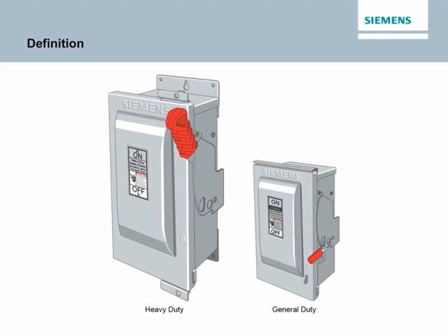A safety switch is a common type of enclosed switch. Safety switches are generally used for 2 purposes: 1, as a disconnecting means for a service entrance, or 2, as a disconnecting means and fault protection for motors. The enclosure provides a degree of protection to personnel against incidental contact with live electrical equipment. It also provides protection to the enclosed equipment against specific environmental conditions. Safety switches may consist of a switch only, or may consist of a switch and fuses. There are 2 families of Siemens safety switches, general and heavy duty.